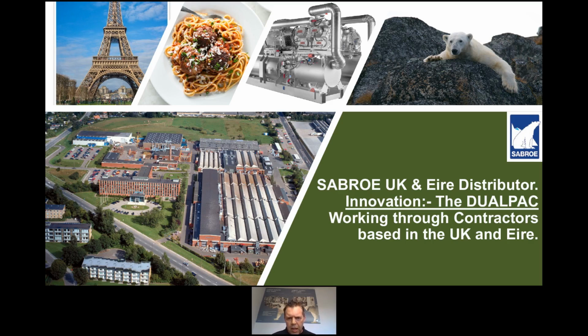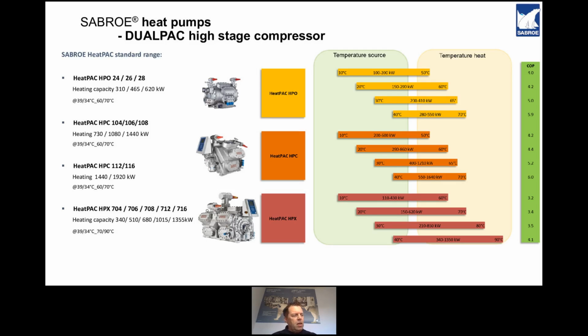So moving on to the next slide, if I can see it here. Here we go. So how do we do this? Basically, this is our range of high pressure reciprocating compressors. To make the dual pack, we take one of our 40 or 60 bar high pressure compressors. That gives us the high temperatures, which you can see 70 degrees, 90 degrees, if you want 90 degrees. And then for the lower side of the 2-stage system, we'll put one of our chiller SMC range compressors. This will extract the heat from air source, water, ground, river source. So you can take those sources and boost them up to 90 degrees if you so wish. So that's that slide.